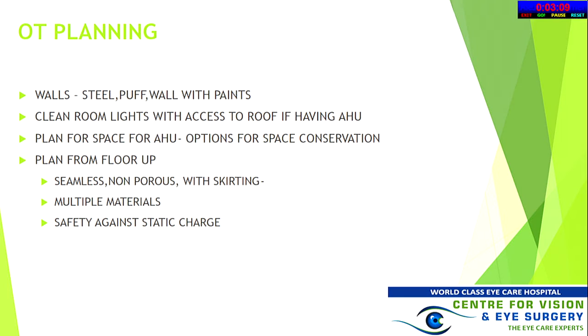It's important that you plan from the floor up. When we planned our operation theater, we did the flooring first because we were putting vinyl on the floor. The vendor said he would need to put a layer of cement on the floor, even though we had tiles, because the sticking is important. He put cement about half a centimeter thick, and on top of that we put the vinyl, which is a good idea because the chance of bubbles under the vinyl is much lower and the stickiness is much better if you do this.